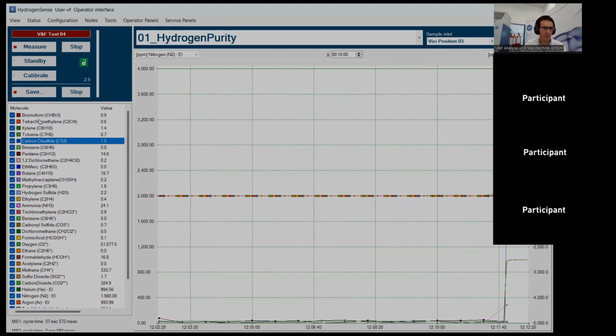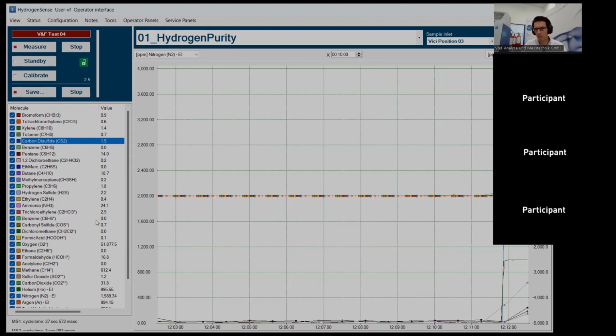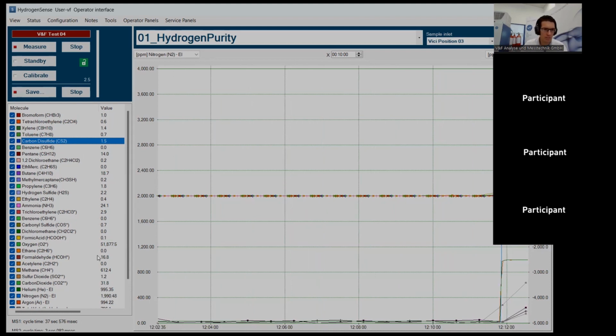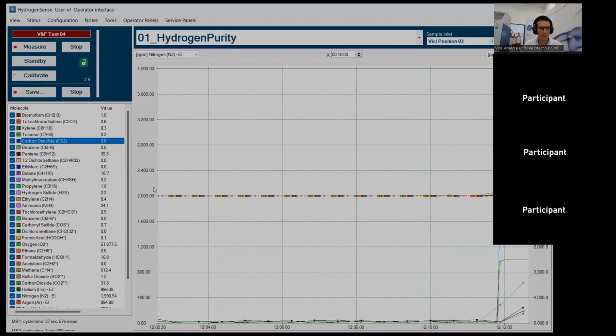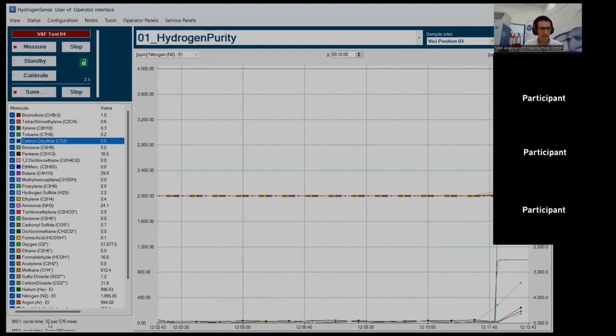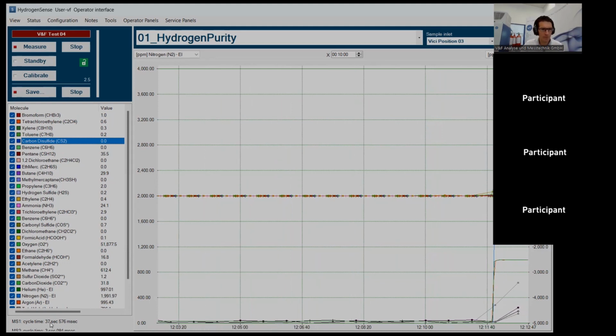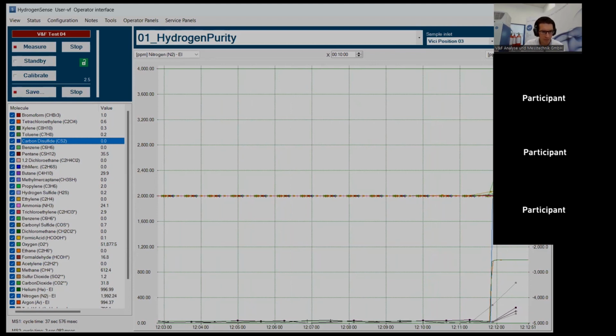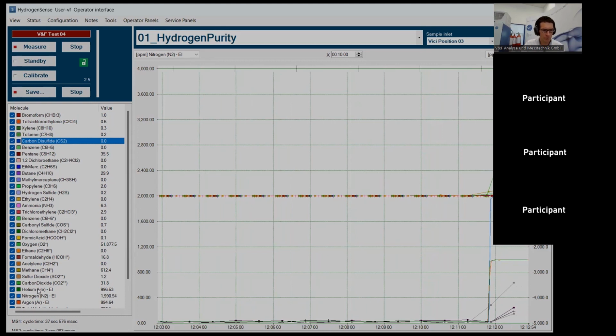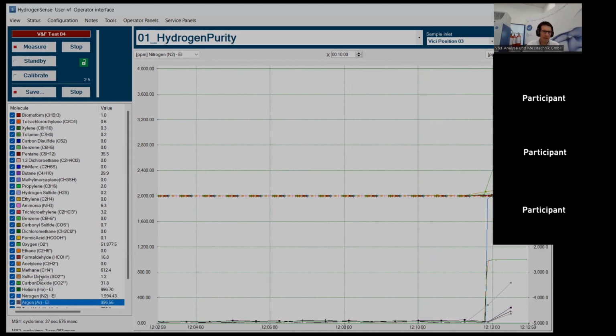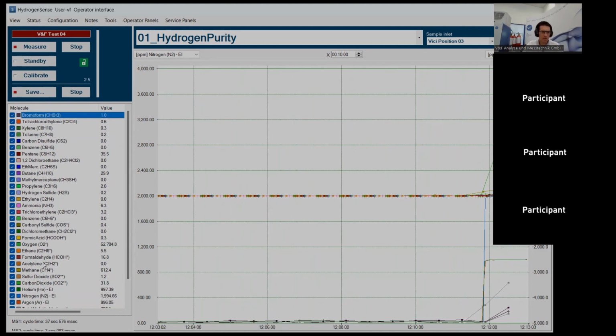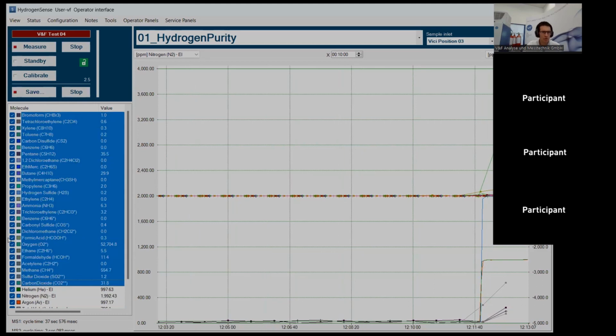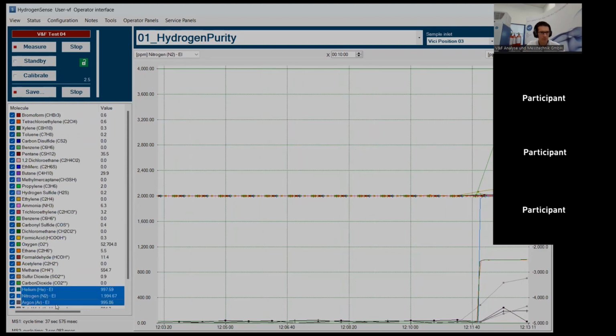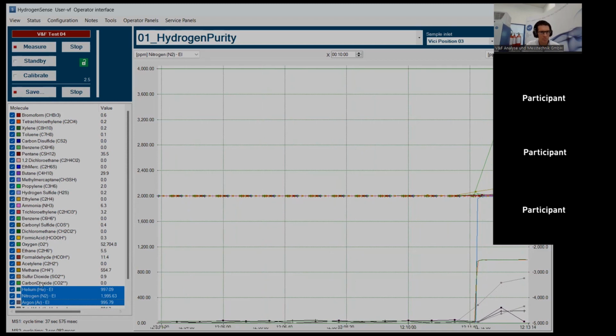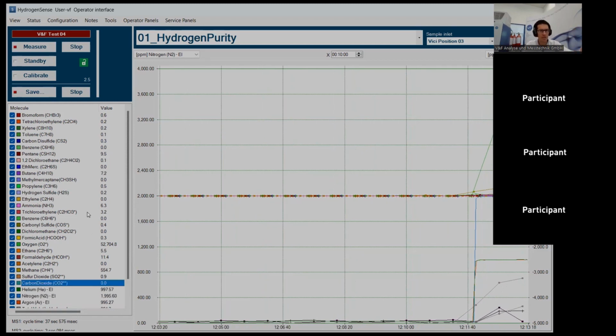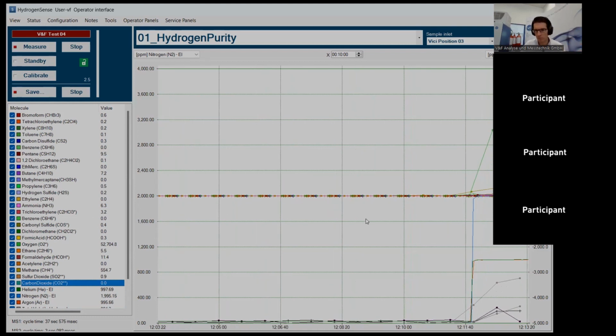So the instrument will go indefinitely from top to bottom and acquire the corresponding signals for the gas which it is currently analyzing. And we see here, right now, we have a single cycle time for the IMRMS spectrometer, which is 37 seconds or 37.5. And we have about 3 seconds for the EIMS molecules. On top, on the surface here, it looks like everything is one cycle, but actually these compounds here are all measured with the ion molecule reaction mass spectrometer, and the bottom 3 here are measured with the EIMS mass spectrometer. So this means that you actually have 2 cycles, and they are then integrated, and the data is collected into the surface that we see here now.